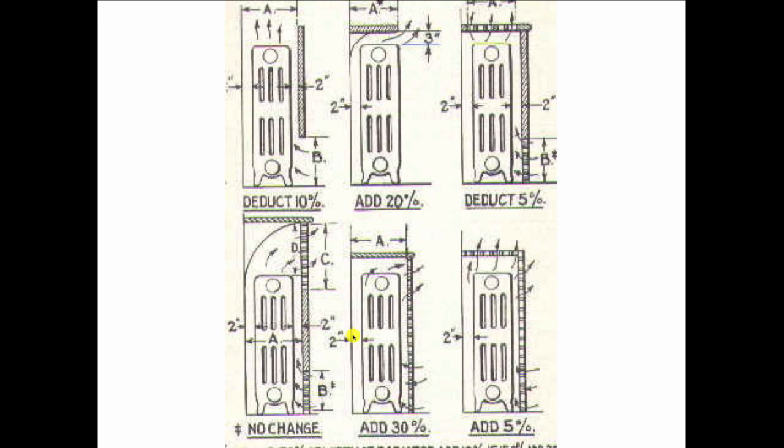If you're ever moving a radiator, keep that in mind. It's supposed to be two inches away from the wall. And again, it's to create that chimney effect of the air moving behind it.